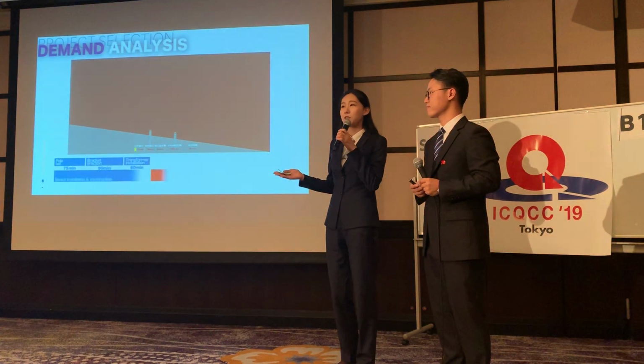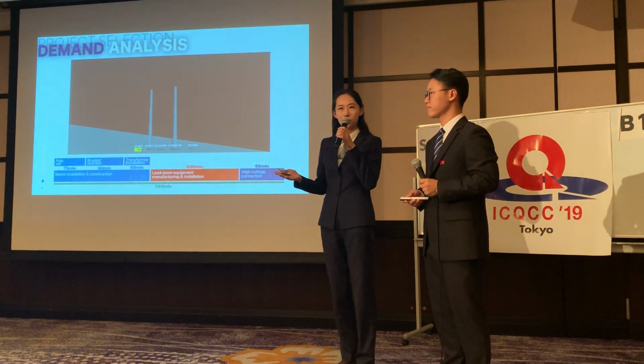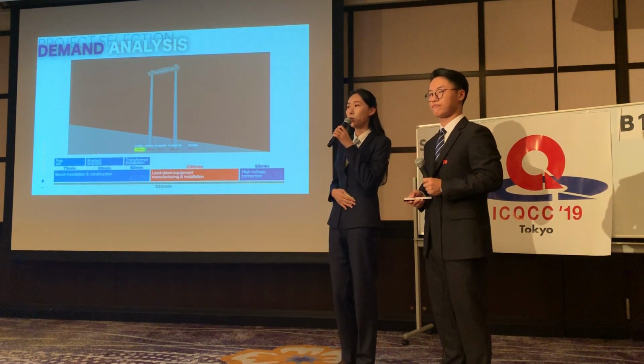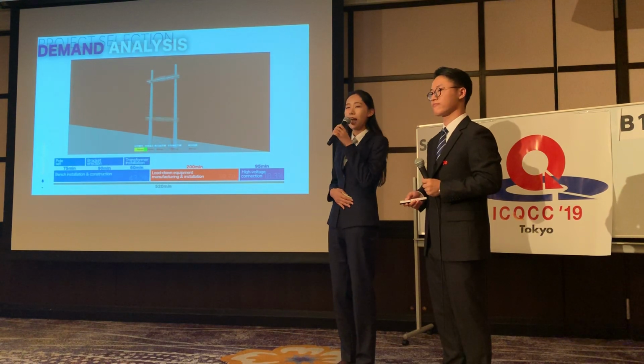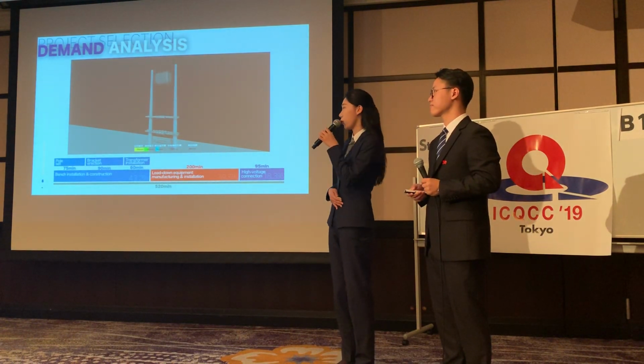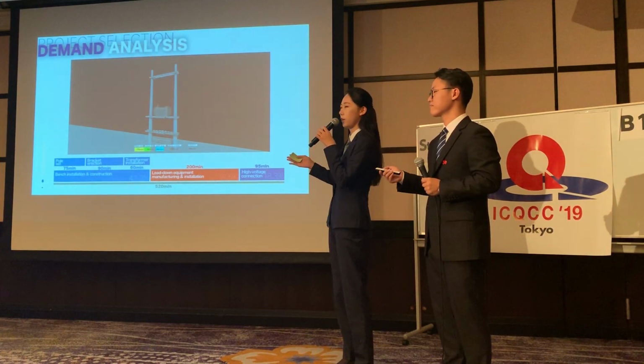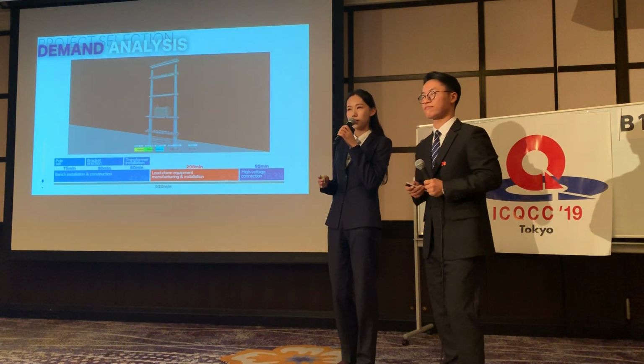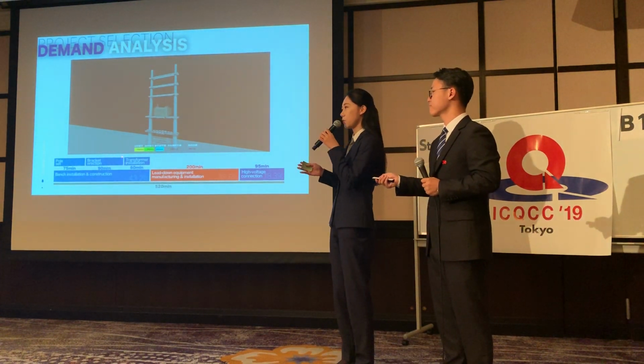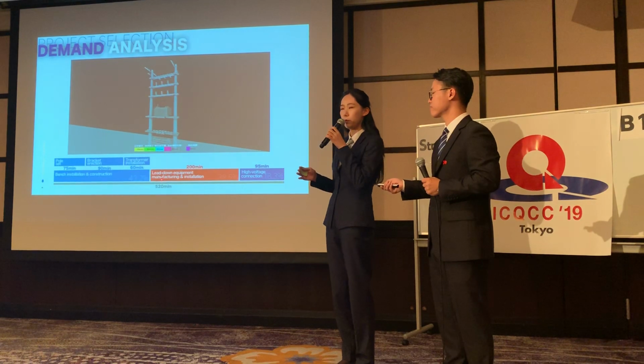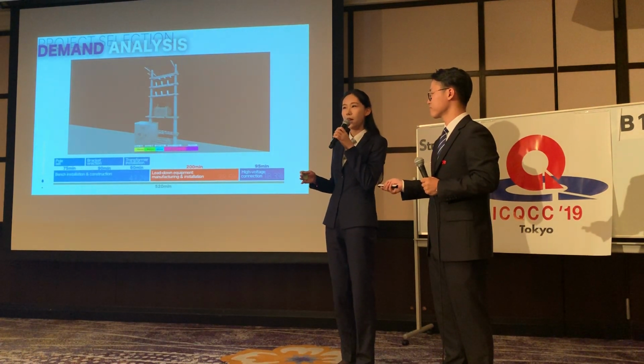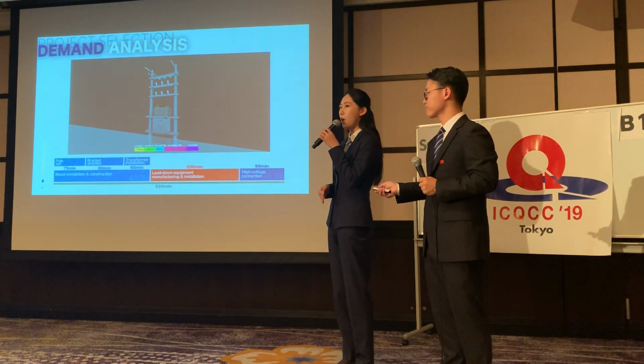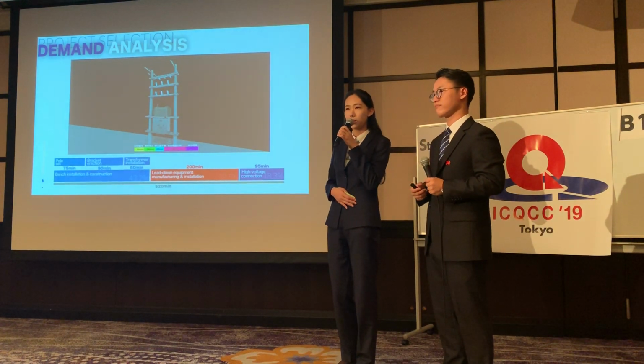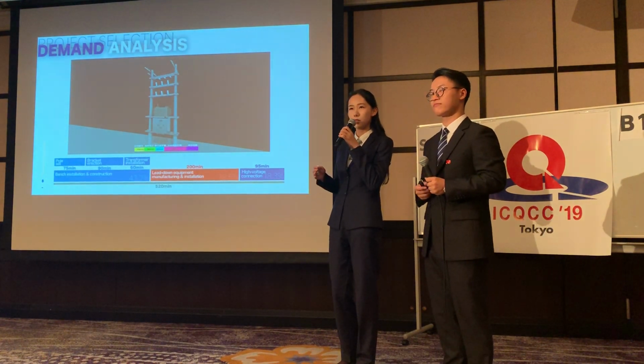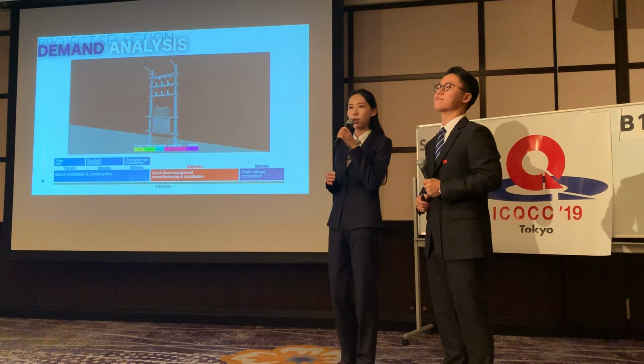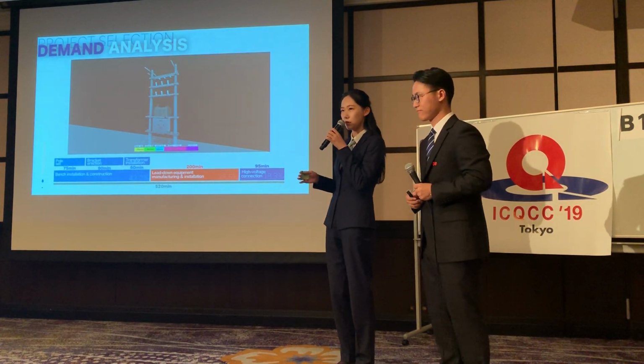Why was the time exceeding the requirement by so much? We analyzed the current engineering methods to find out. At the time, the engineering methods were mainly divided into 5 steps: pole setting, bracket erecting, transformer installation, lead-down equipment manufacturing and installation, and high voltage connection. Among them, 4 out of 5 are constructed via crane. Once installed and assembled, there is basically no space for time-saving measures.